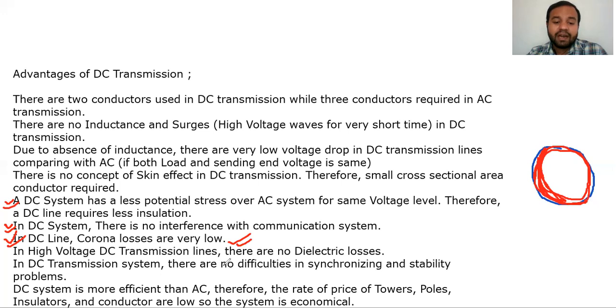In a DC transmission, there is no difficulty in synchronizing and no stability problem. In AC, there is definitely a synchronizing problem — if a system works at frequency 50 hertz, two systems can be synchronized only when their frequencies closely match. We do have methods for that, but synchronization is only possible when the frequency match is there. So synchronization problem is not there in a DC system, and since synchronization problem is not there, stability problems are also not there with DC. That is the advantage of DC.